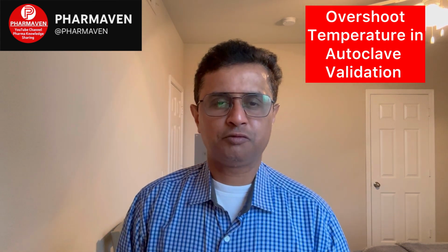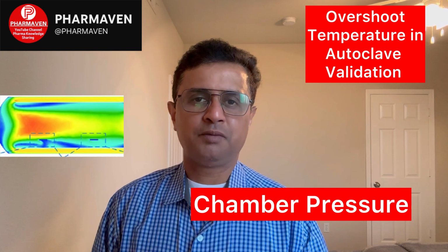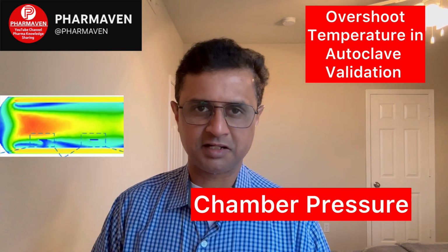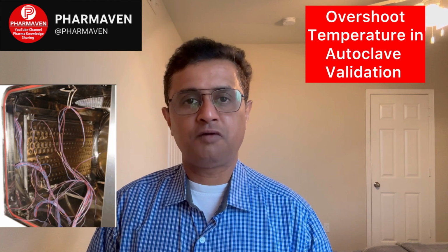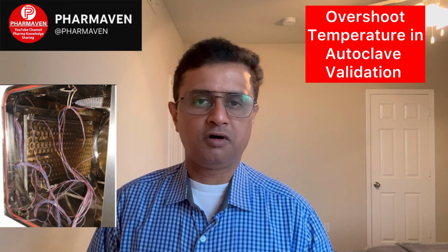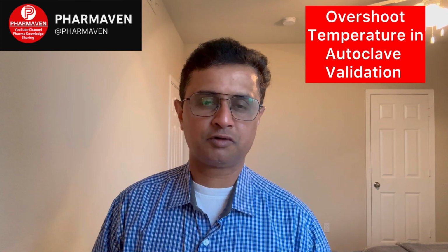So first check what the pressure was during that specific time and compare that cycle with another good cycle, the previous validation cycle, to see whether there is any change in pressure, whether the pressure parameters are similar or there is a change. If there is a higher pressure during that specific time, that could have led to the overshoot temperature. Secondly, check the temperature data of all the sensors in the load. Not all might have gone to overshoot, but if the temperature is overall on the higher side compared to the previous validation cycle, then it shows that this cycle has some specific issue and not the autoclave performance. So we can compare the data and, on that basis, decide what might have gone wrong with this specific cycle.